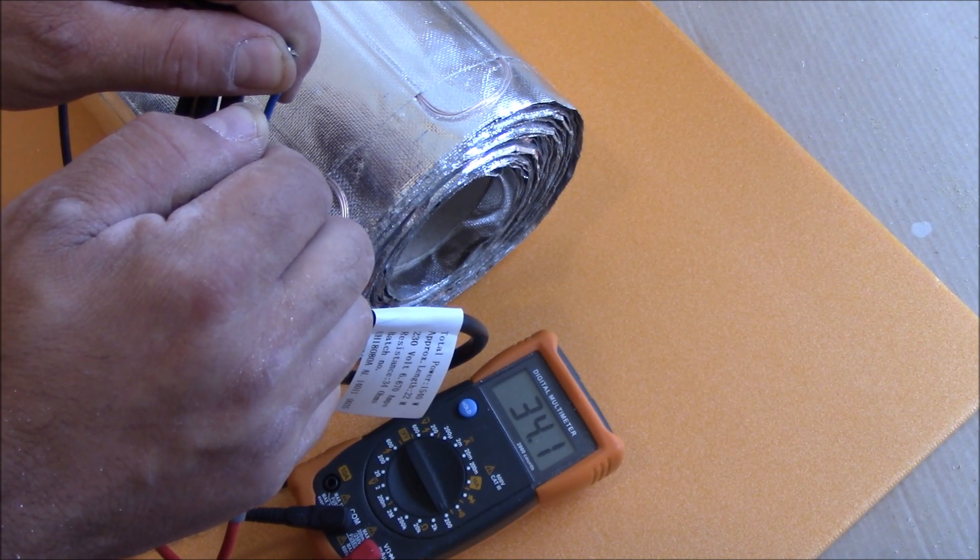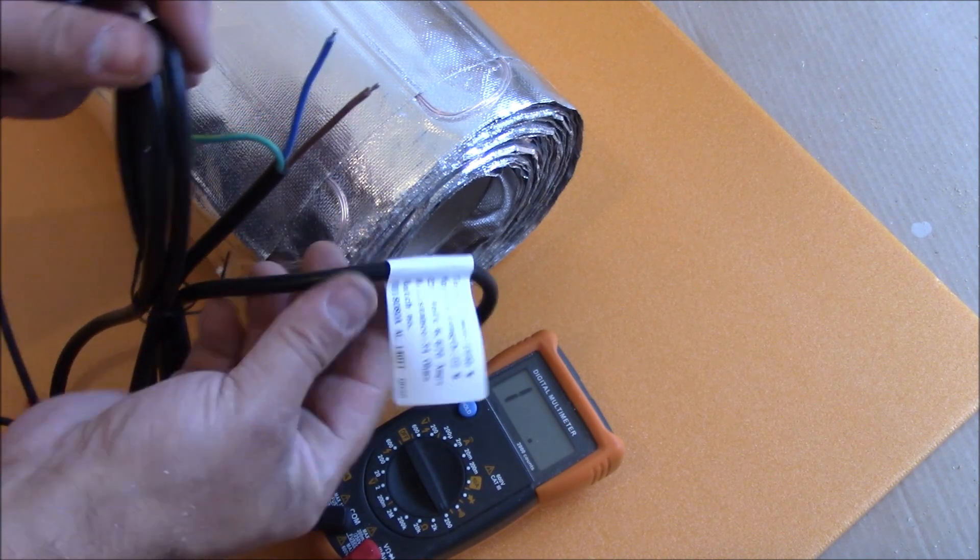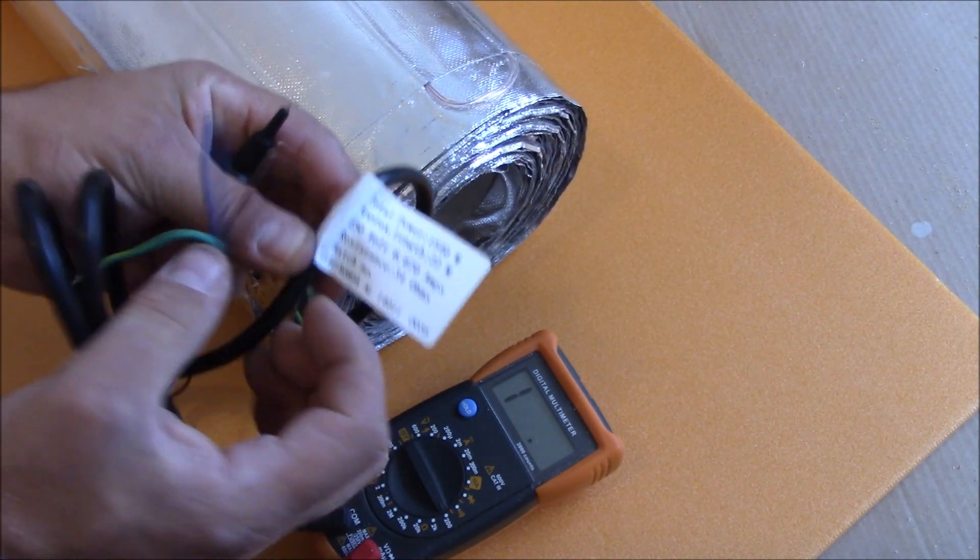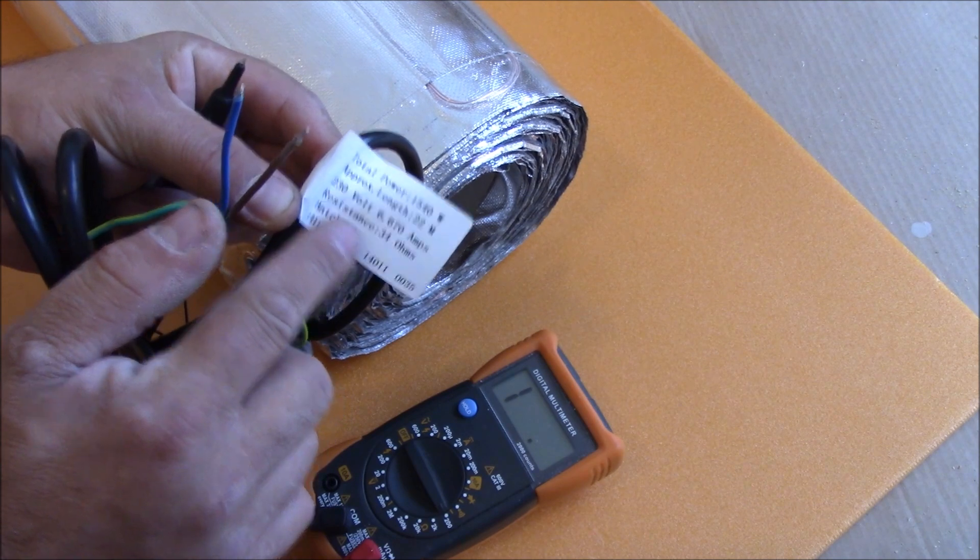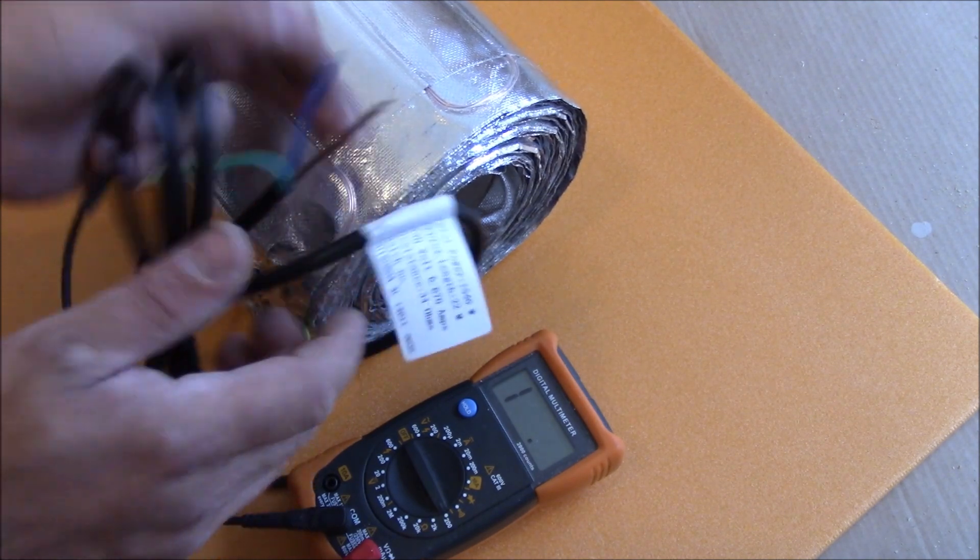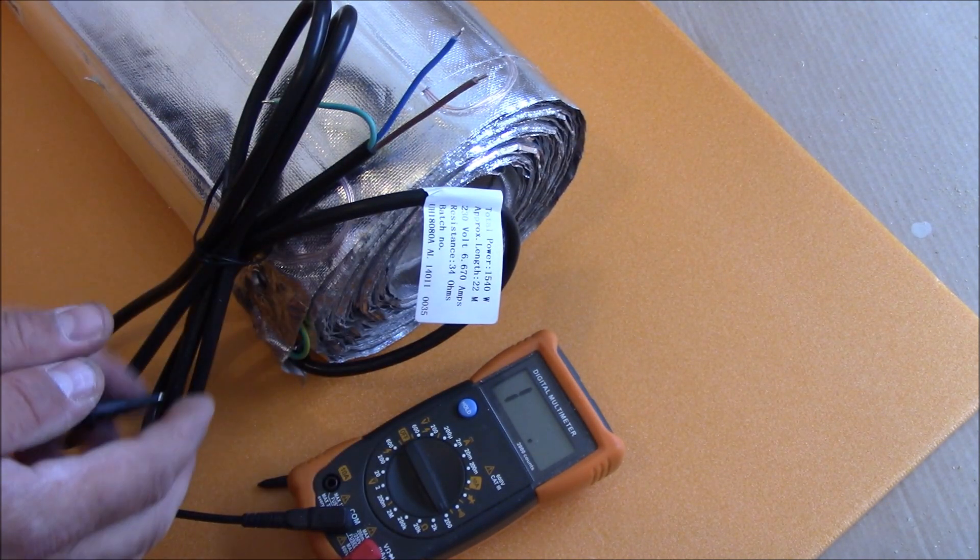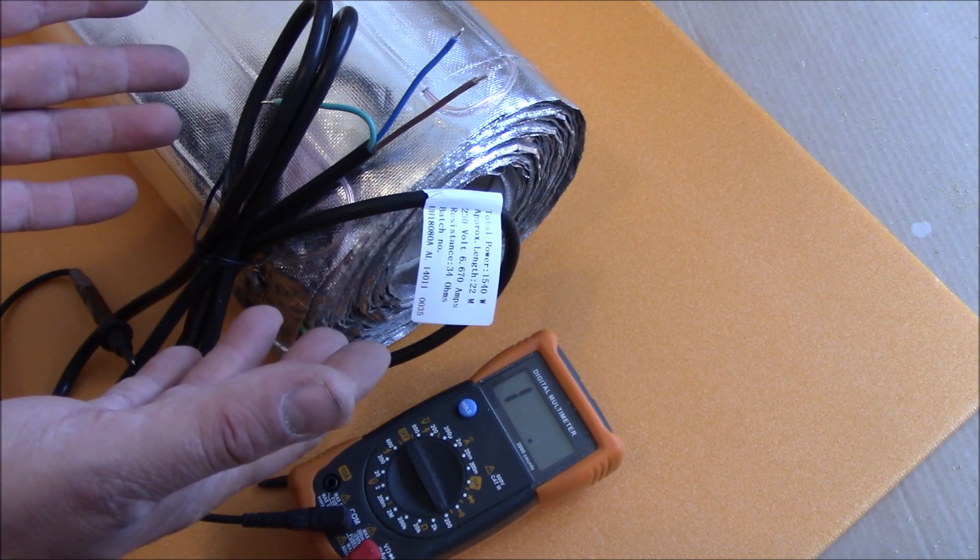34.1 ohms. Let's check again on the label. Yeah, that should be 34 ohms. So that means that this mat is not damaged so we can lay it onto the floor.